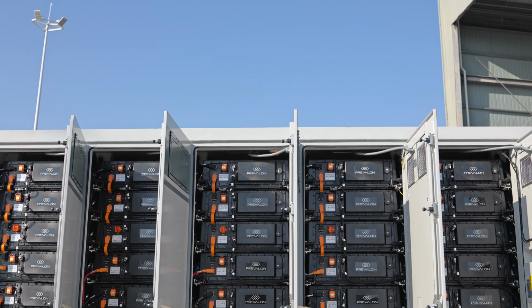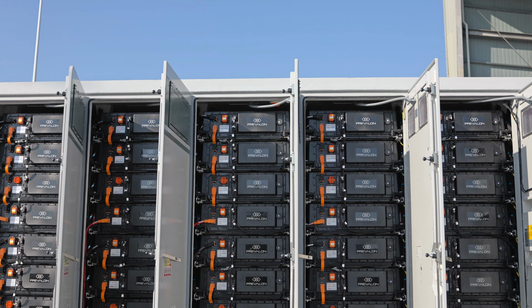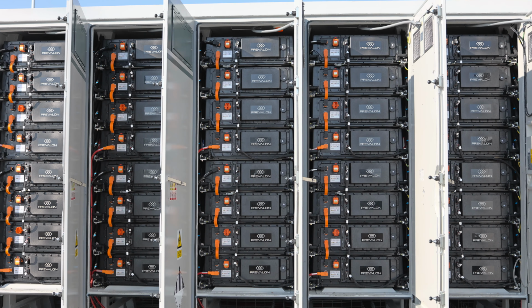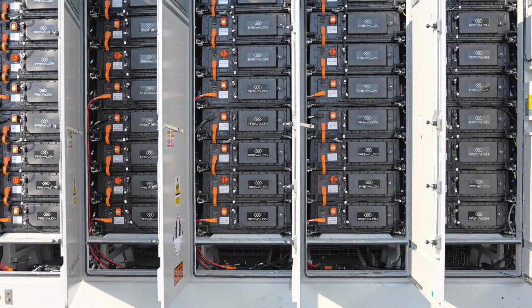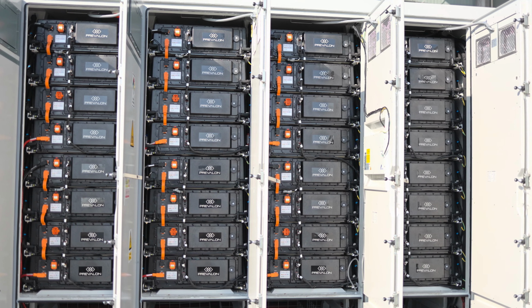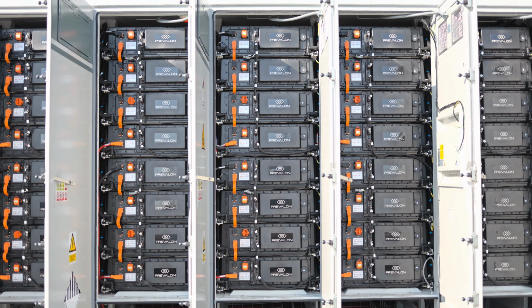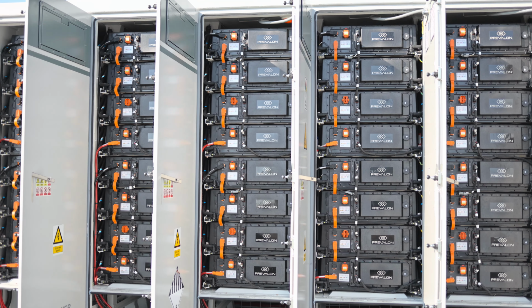The battery compartment contains the LFP battery modules and string BMS controllers. There are 6 rack structures, each containing 2 battery strings for a total of 12 strings, adding up to 5 megawatt hours.